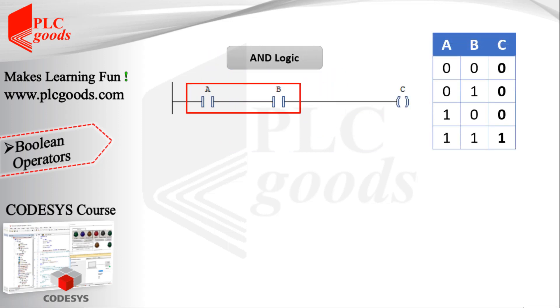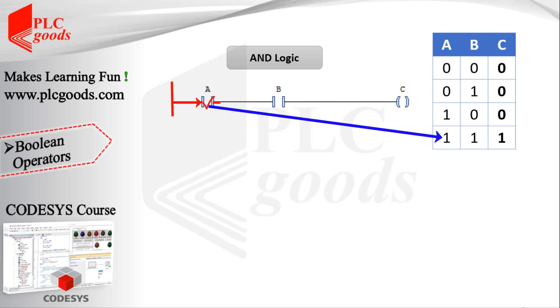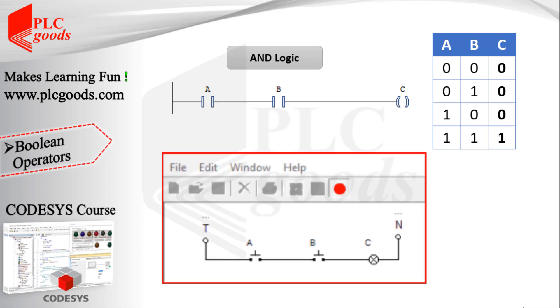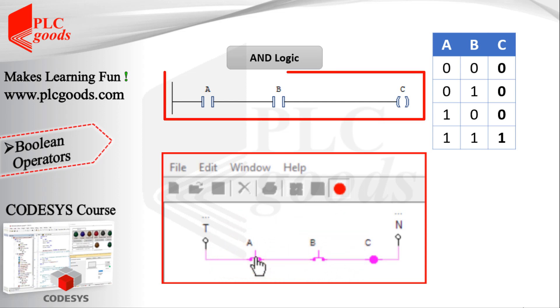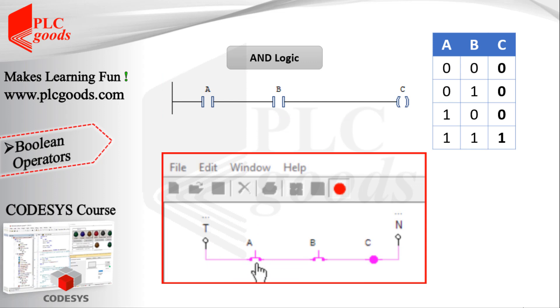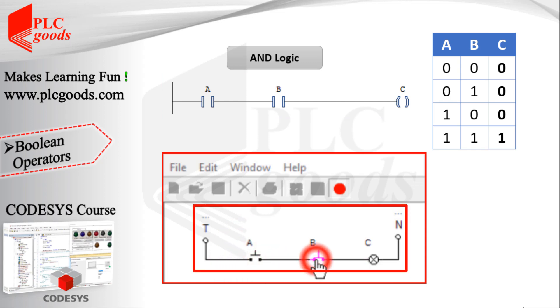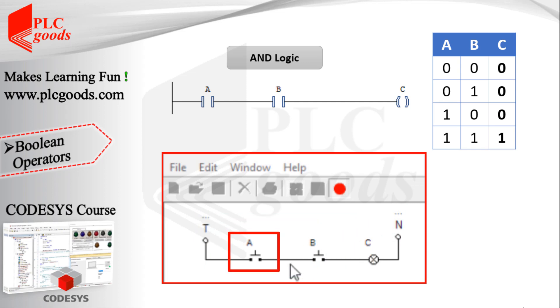For example, I can change this program easily and use A and B contacts in this form to turn on the output C. This program is known as AND logic, because the output will be on if and only if both contacts A and B are activated. At the bottom, its equivalent circuit is shown for testing. Compared to the previous slide, the PLC program has been changed easily, but the electrical circuit wiring has also been changed and a normally closed push button has been replaced by a normally open type.